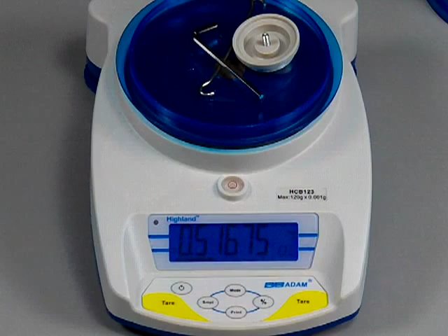We also have the print parameters where you could set your baud rate, your parity. That's also used if you're using the RS-232 interface. We have the auto off parameter, where when the balance is not plugged into an AC adapter and is on battery power, you can set it up so the scale automatically shuts off after 5, 10, or 20 minutes.